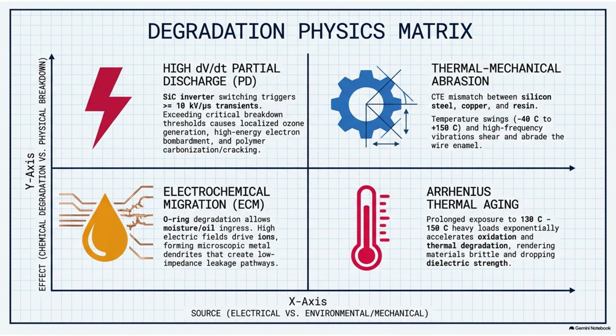10,000 volts in a single microsecond. To a non-engineer, I mean, that just sounds like a big number, but dynamically, what does that actually do to a wire? It creates severe wave reflections. Think of the electrical pulse leaving the inverter like a heavy battle rope tied to a concrete wall. Okay, yeah. When you whip that rope, a wave travels down its length. When the wave hits the rigid wall, which in this case is the impedance mismatch at the motor terminals, it doesn't just stop. Right, it snaps back. Exactly. The reflecting wave collides with the next incoming wave from the inverter. Ah, so they stack on top of each other. Precisely. You get localized voltage doubling.